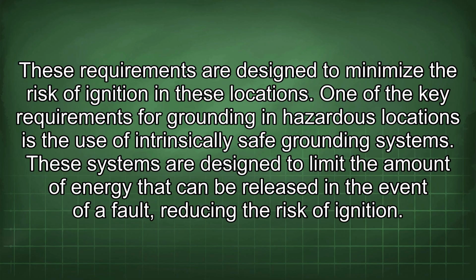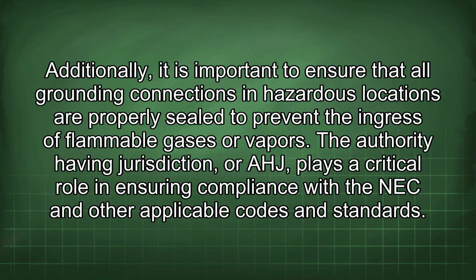One of the key requirements for grounding in hazardous locations is the use of intrinsically safe grounding systems. These systems are designed to limit the amount of energy that can be released in the event of a fault, reducing the risk of ignition. Additionally, it is important to ensure that all grounding connections in hazardous locations are properly sealed to prevent the ingress of flammable gases or vapors.